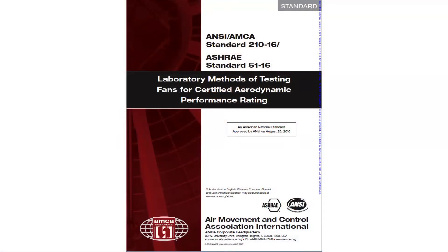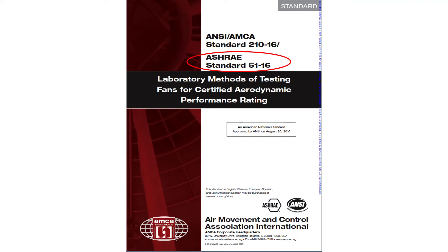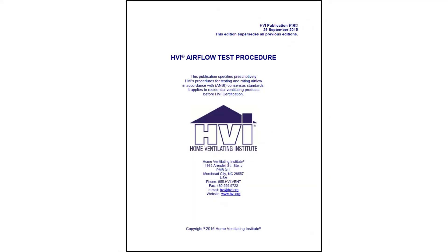Interesting. So does this type of measurement system adhere to any industry standards? Yes, actually it adheres to several standards. First, there's the Air Movement and Control Association, AMCA — this is standard 210. Also, there's the American Society of Heating, Refrigerating, and Air Conditioning Engineers, ASHRAE, standard 51. There's also the Home Ventilating Institute, publication 916, used to measure vents and grills used in HVAC systems.